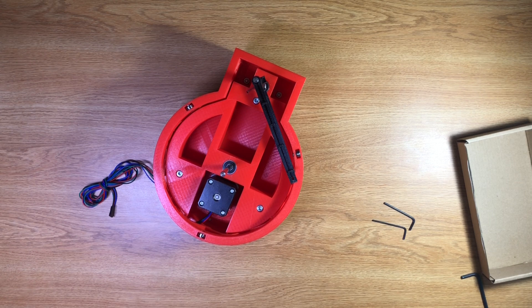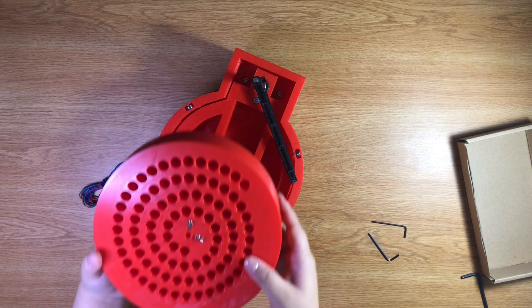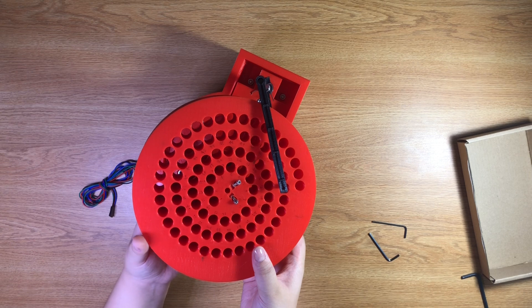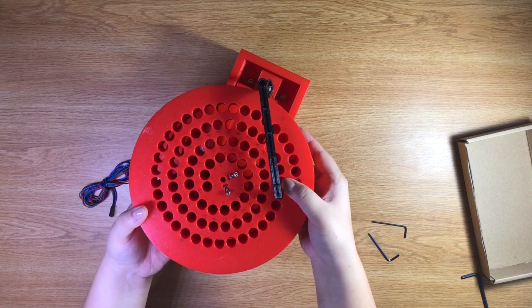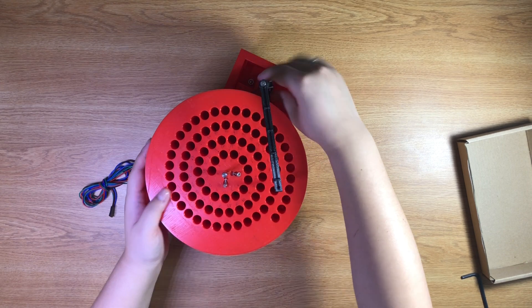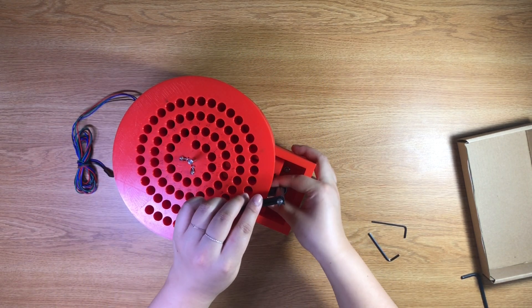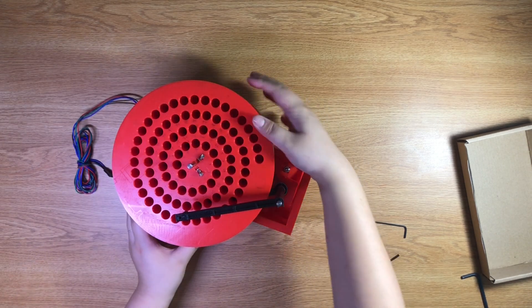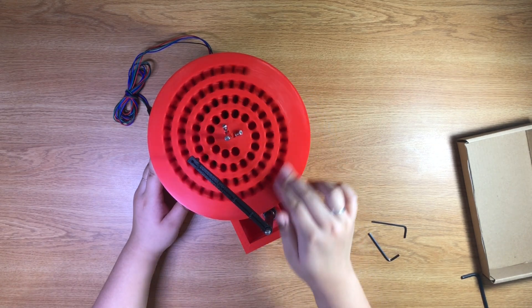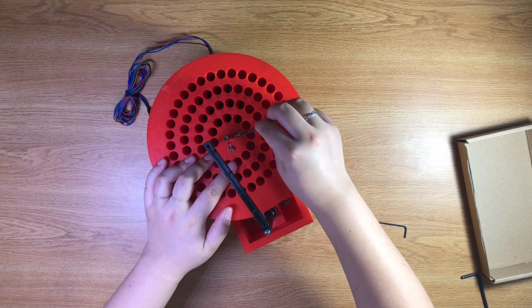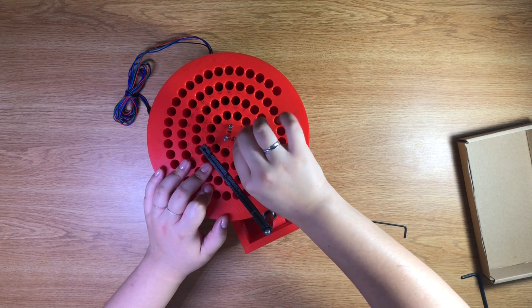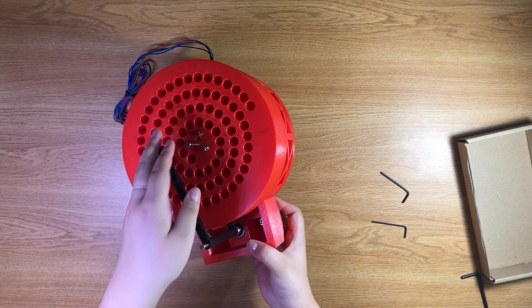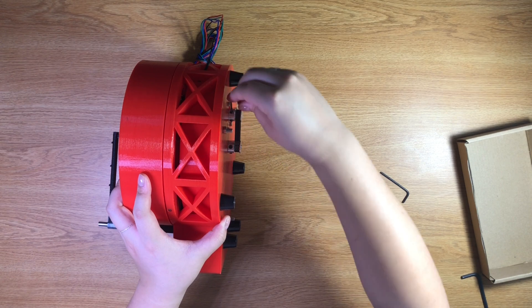Insert the rotary shaft into the center ball bearing. Take the tube bed and carefully push it through the shaft. It might be easier to lift the arm off the base plate to do this. Press down the tube bed until it touches the base and make sure the torsion spring on the arm is properly fixed onto the base plate. Also, make sure that the ball bearing on the arm is touching the spiral grooves of the tube bed. If everything is correct, then you will see the arm rotate with the tube bed as you spin the tube bed around. Tighten the set screws on the tube bed. Turn the device upside down and make sure the set screws on the pulleys are tight.